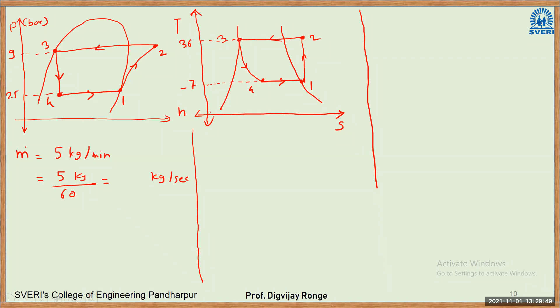Meanwhile, I will put the values here. In this case, the condenser pressure is 9 bar, and the evaporation pressure is 2.5 bar. The temperature at condenser pressure is 36 degrees Celsius, and here it is -7 degrees Celsius. Have you calculated the mass flow rate? Good, 0.0833. So this will be the mass flow rate.